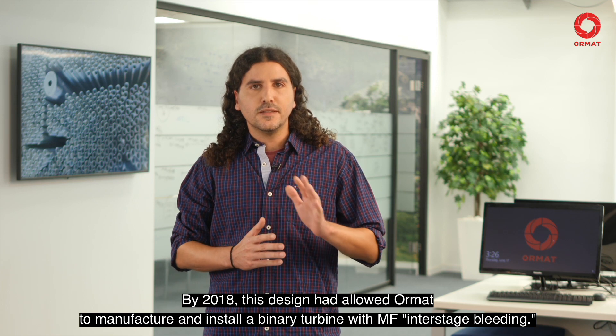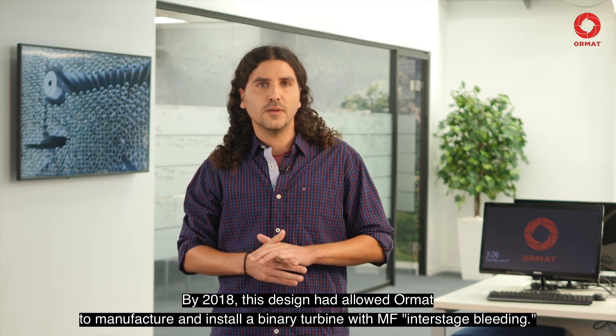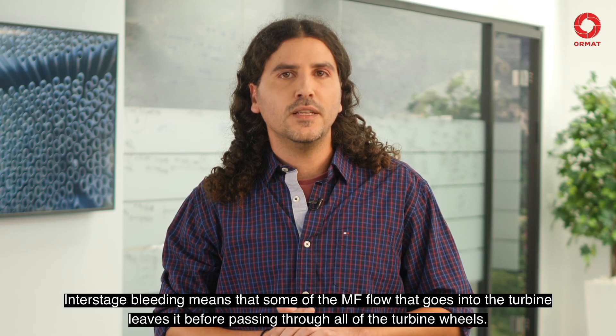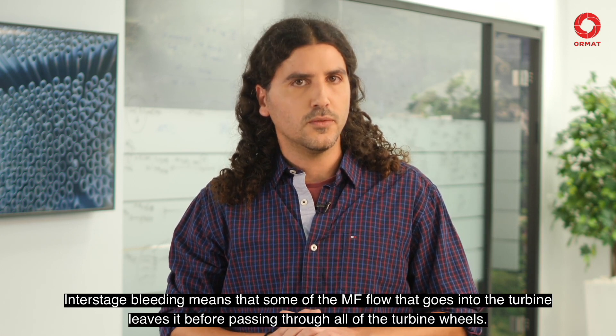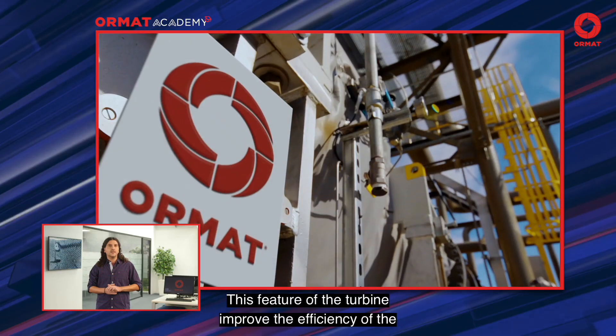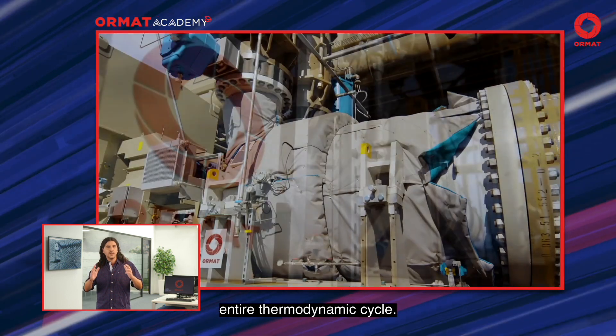By 2018, this design allowed Ormat to manufacture and install a binary turbine with motive fluid interstage bleeding. Interstage bleeding means that some of the motive fluid flow that goes into the turbine leaves it before passing through all of the turbine's wheels. This feature of the turbine improved the efficiency of the entire thermodynamic cycle.